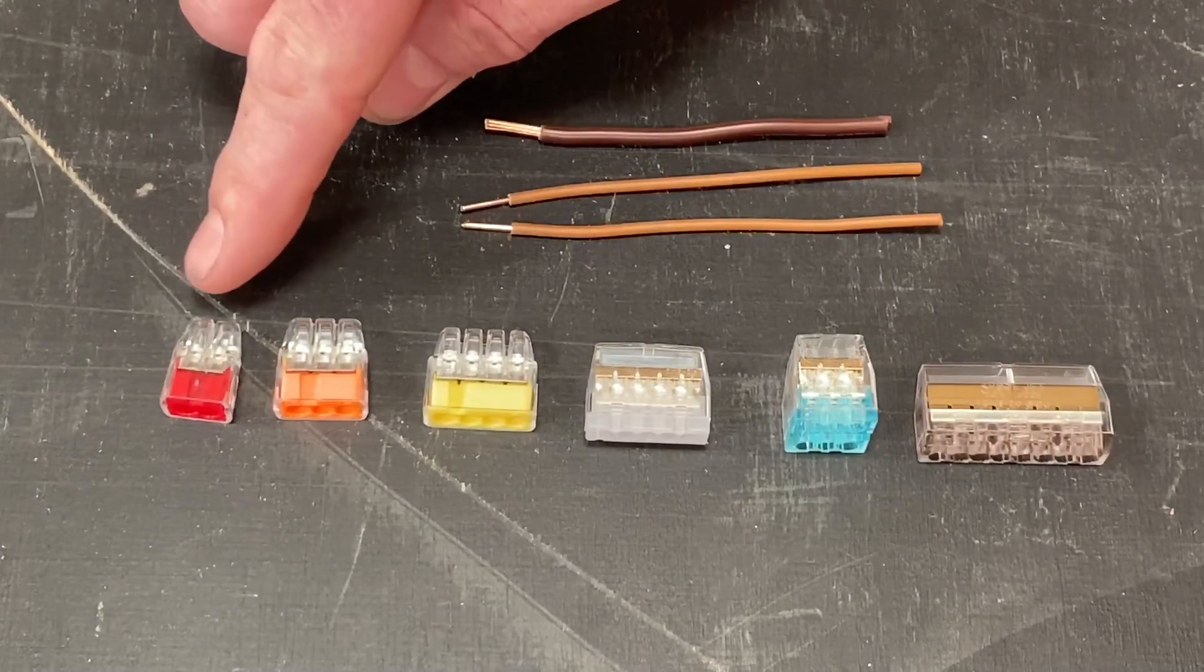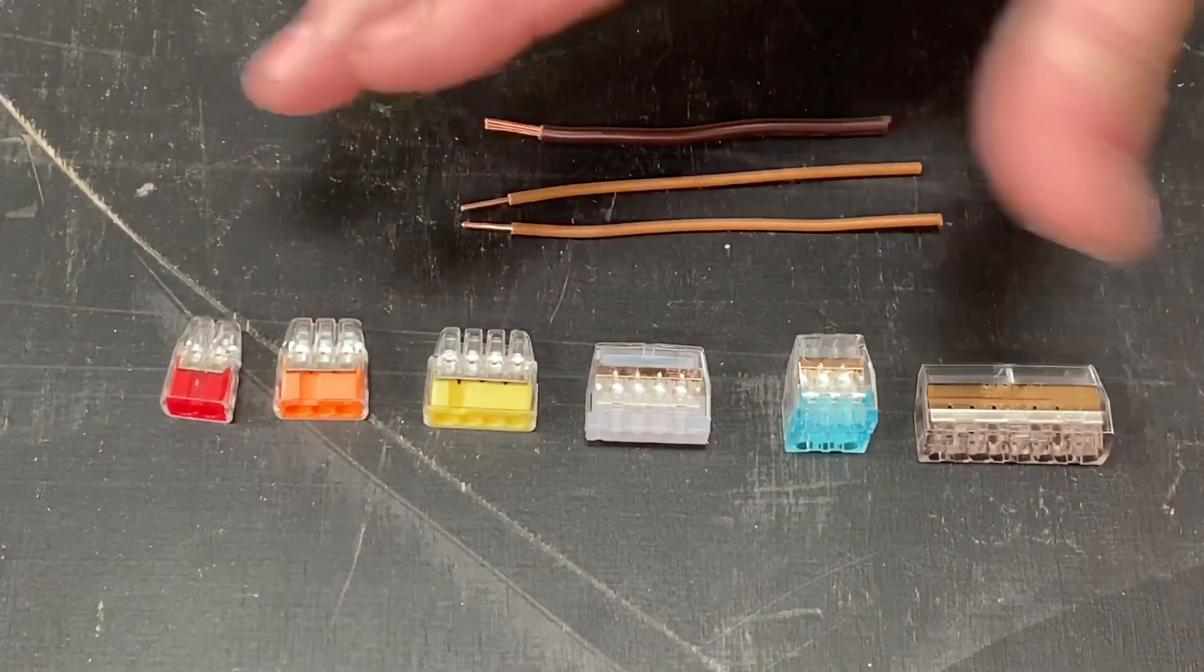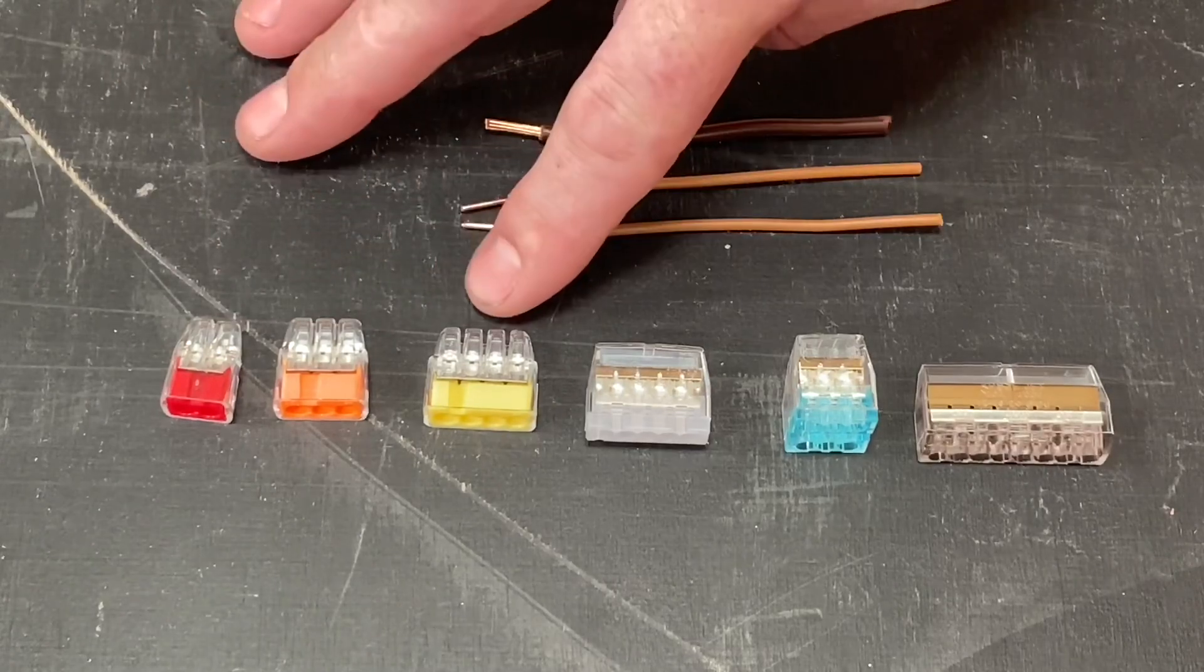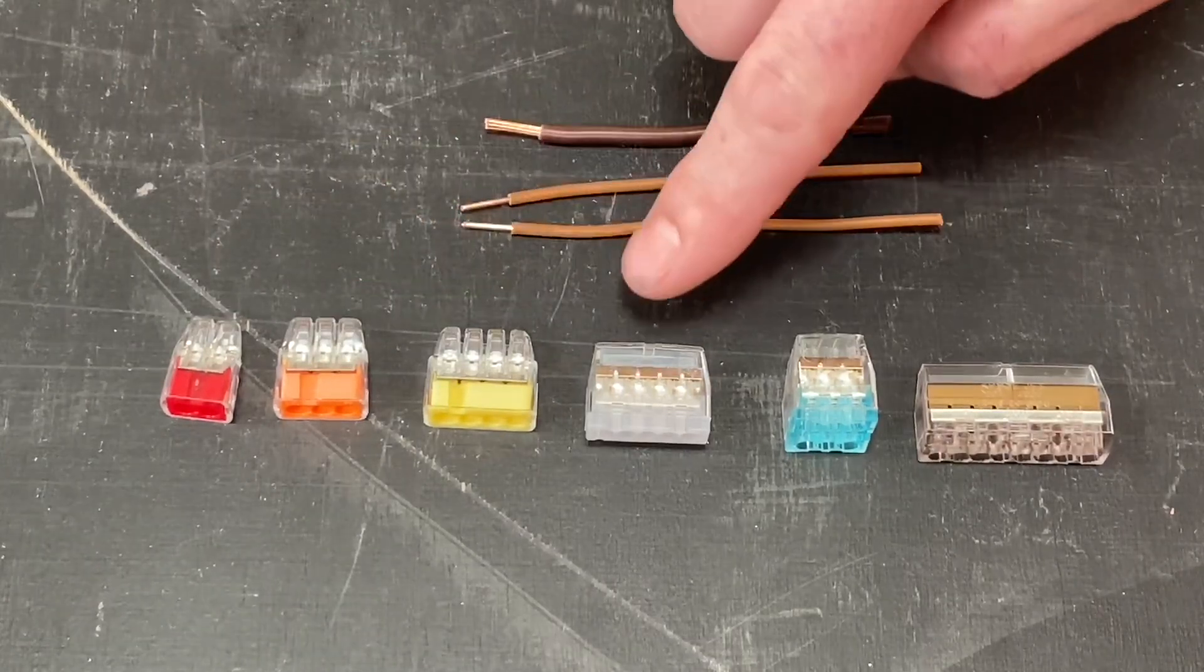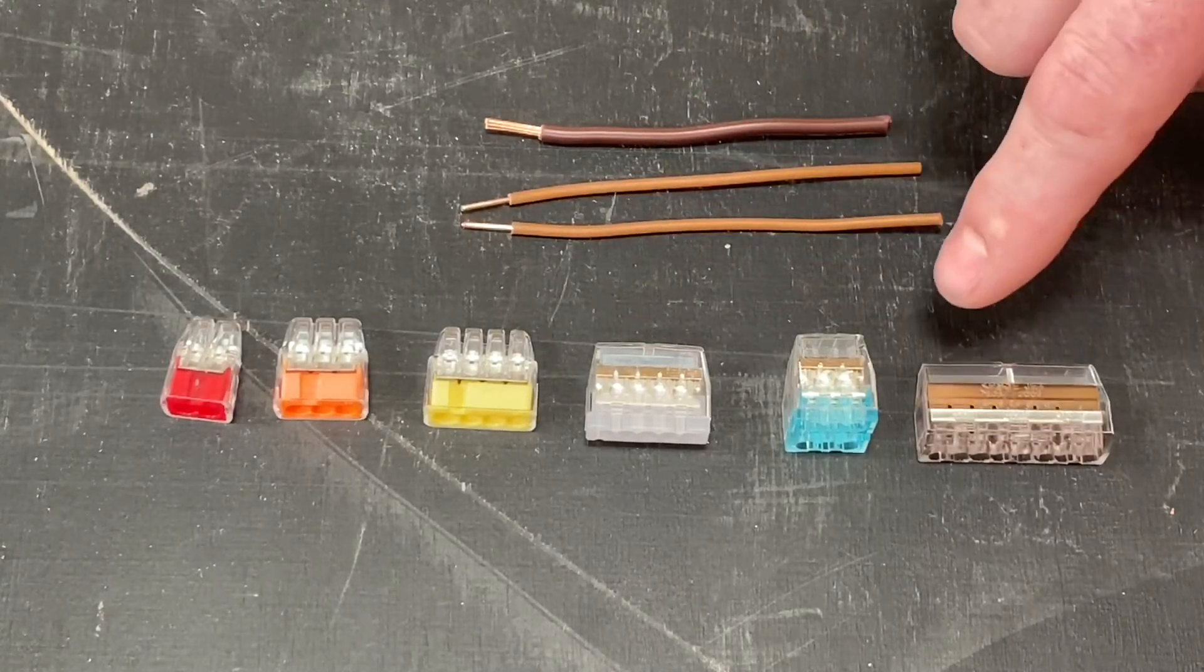So now we're on to our push-fit connectors with two, three, four, five, six, and eight conductor connectors. The two, the three, and the four have a current rating of 32 amps, and the five, six, and eight have a current rating of 24 amps.